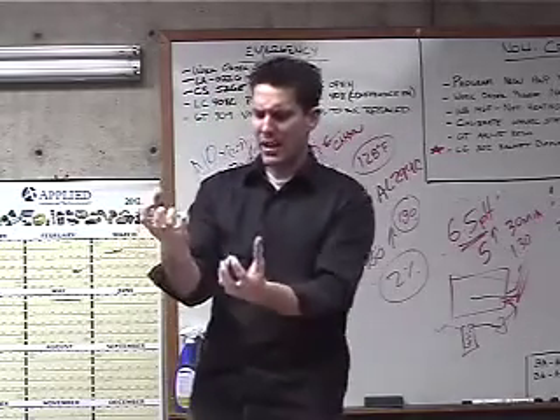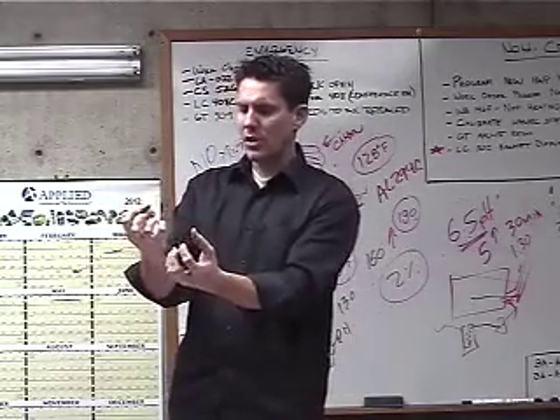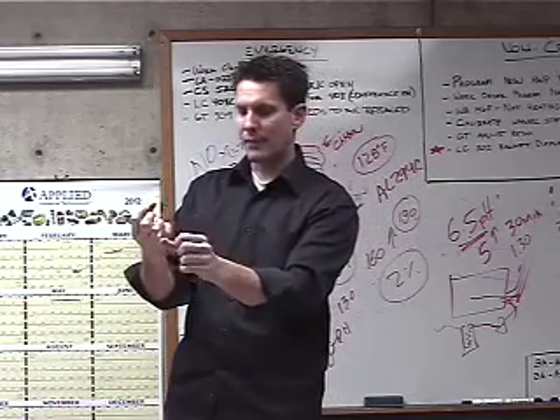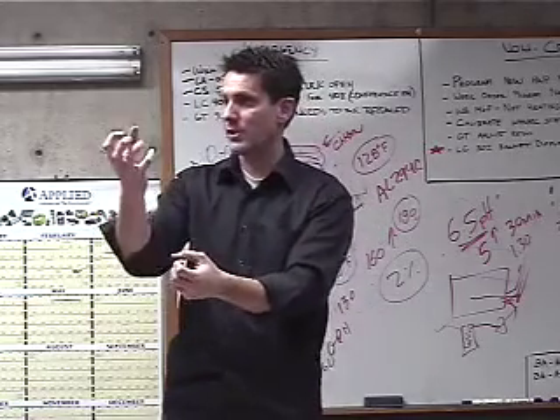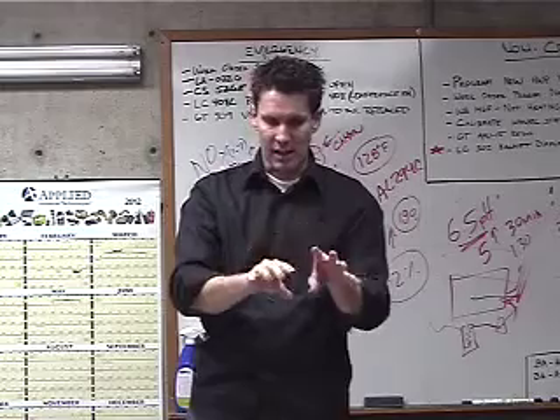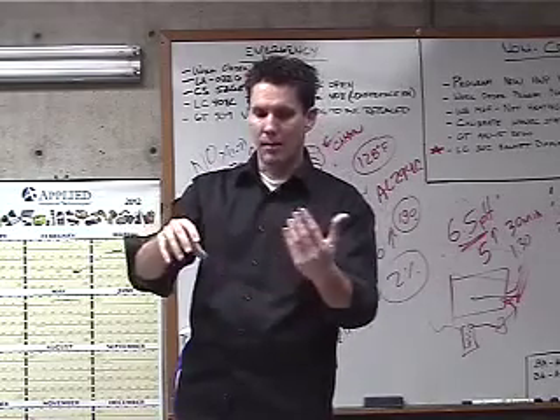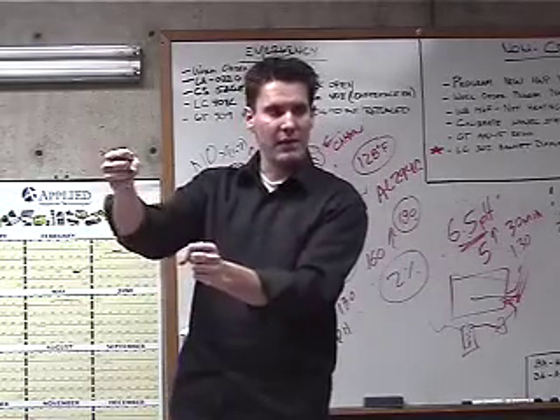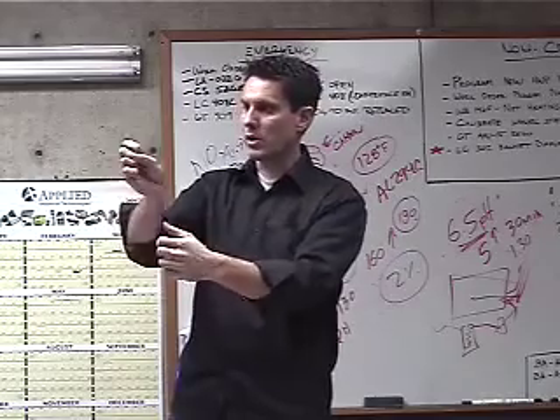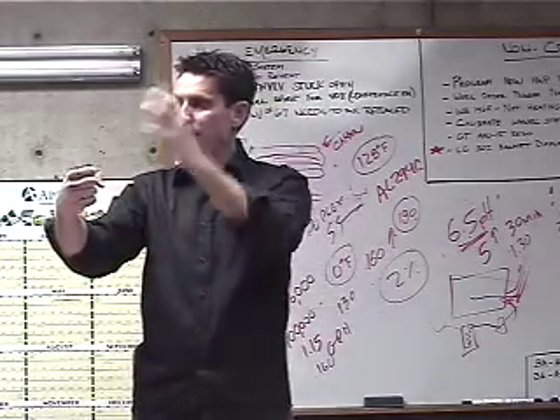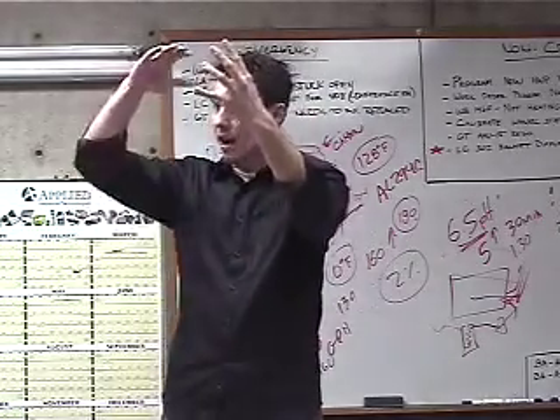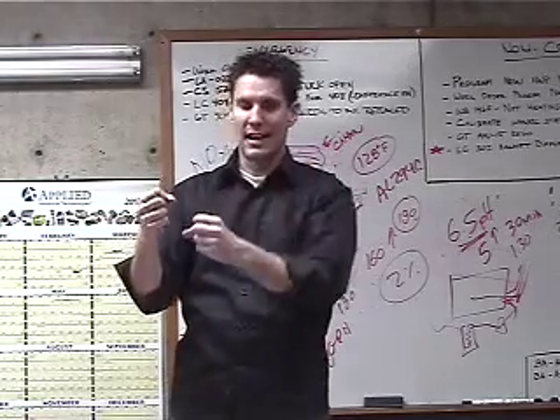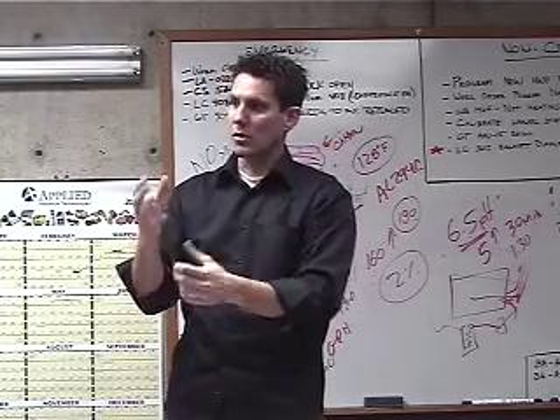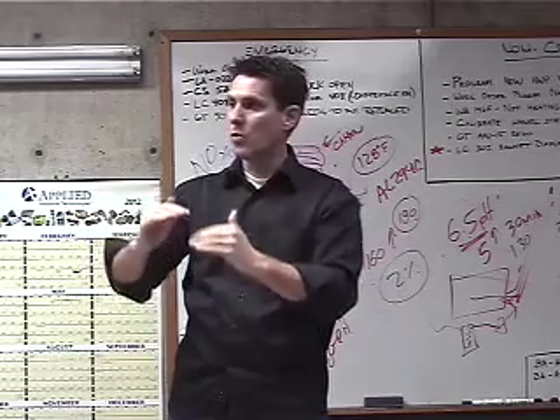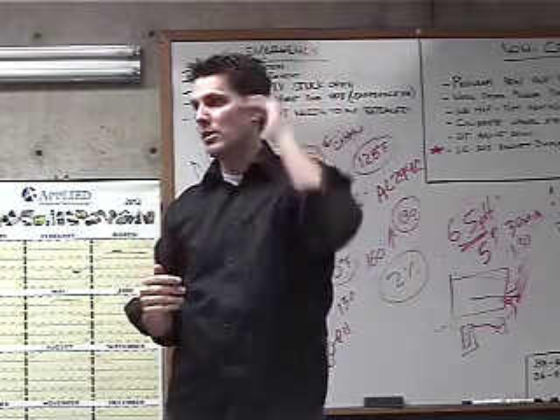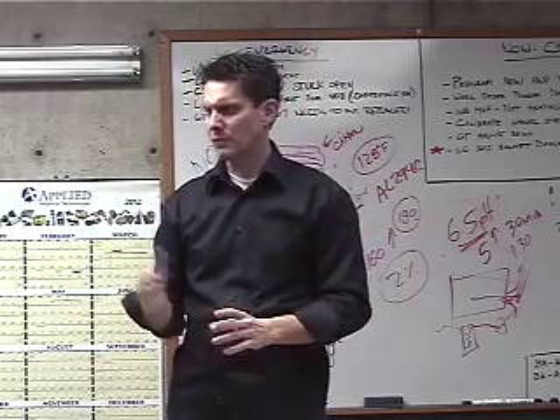And what it's doing is you've got a gas valve, not the gas valve itself, but what they call a gas servo valve and an air servo valve. As we set this up electronically, it sends out a 4 to 20 milliamp signal to both of these valves so they modulate together. So we're limiting the amount of air. The fan's still the same speed, but we're limiting the amount of oxygen that's coming in through this air servo valve, and same thing with the gas. So we're maintaining that same 10-to-1 ratio from high fire all the way down to low fire. Does that answer your question?